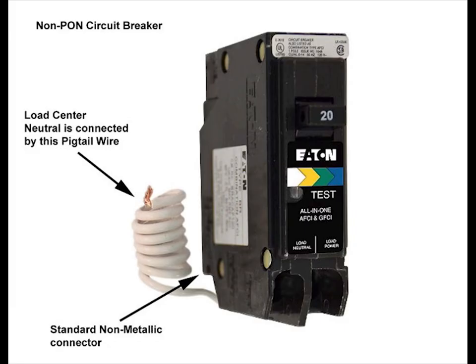You can put a ground fault interrupt and/or an arc fault circuit breaker into a non-plug-on neutral load center. Again, there's only one metal connector on the back of the circuit breaker. This is for the power connection. The circuit breaker hooks into the load center with a non-metallic, non-conducting hook. There is a white pigtail wire that will attach to the load center neutral or load center ground. This circuit breaker has two screws for wire attachment, load power for the black wire and neutral for the white wire.